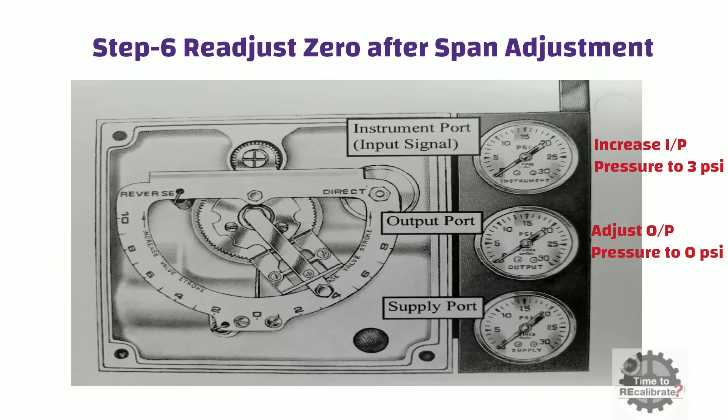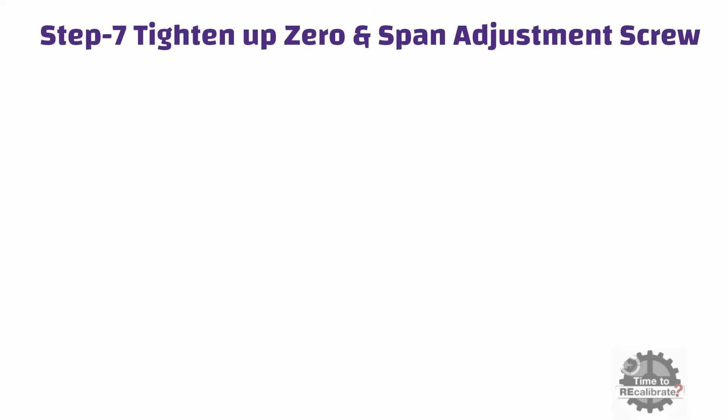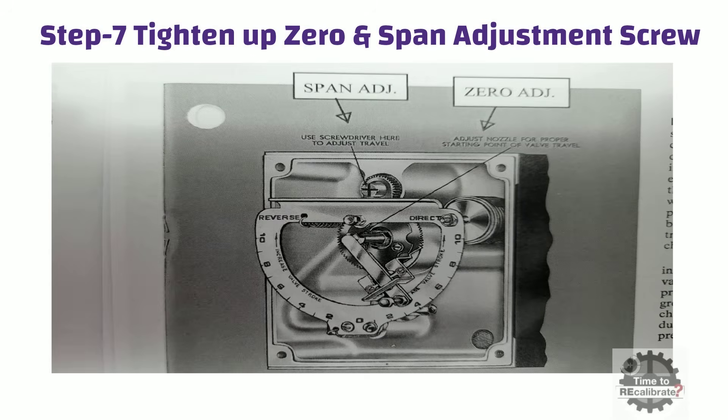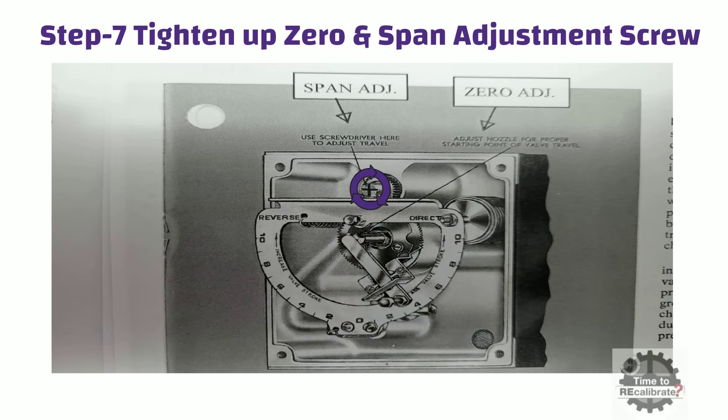When the Fisher 3582 valve is fully calibrated, we can be sure that when input signal is 3 to 15 psi, the control valve is either fully open or fully closed. Once you are done with zero and span adjustment, don't forget to tighten up the zero and span adjustment screws. This is also an essential step — if you forget to tighten them after calibration, your zero and span adjustment may be disturbed.